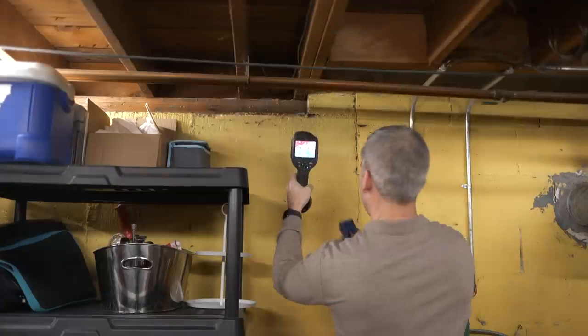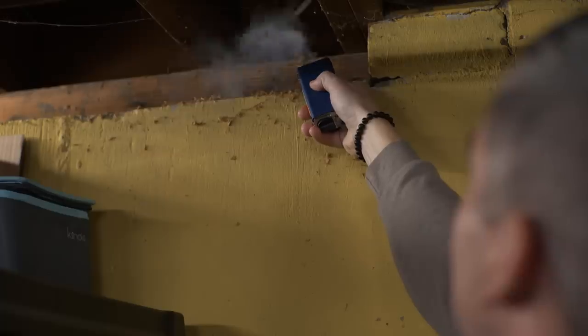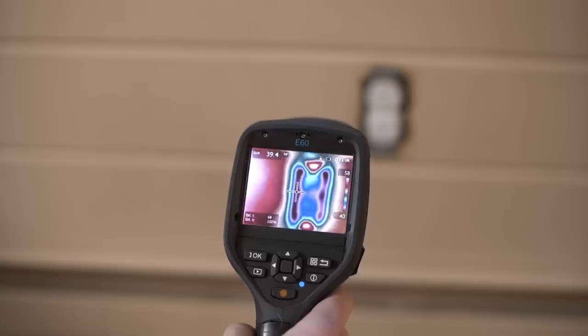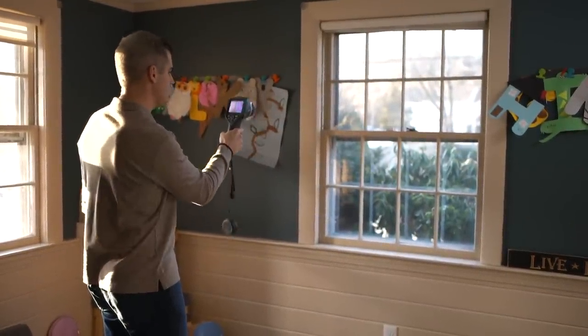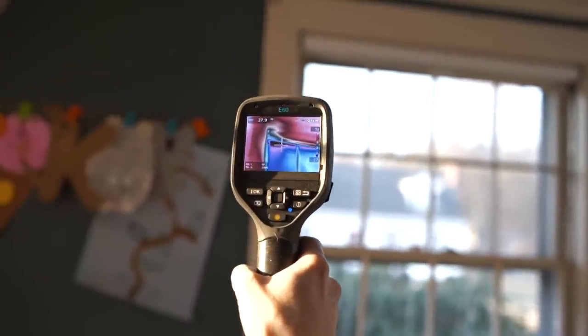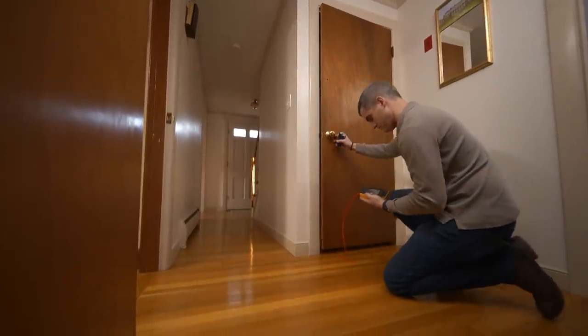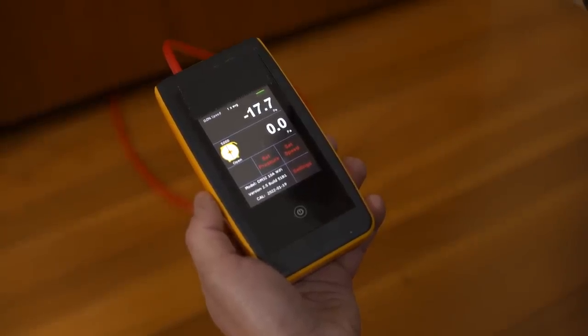As I conduct the blower door test, I will look to see where air is being pulled. I hope to determine two things: how leaky is each room, and where are the leaks coming from? The thermal imaging camera visualizes heat flow by showing the relative temperature on surfaces — the darker the color, the colder the air. So blues, purples, and blacks would be indicative of cold air coming in from outside. A manometer measures the pressure differential between rooms and helps determine how leaky particular areas are within the house. This is called zonal pressure testing.